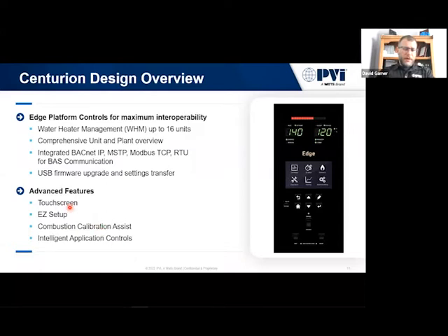The other key feature I really want to talk about is the easy setup. This is taking advantage of the O2 trim system in the unit. So let's say there's a job site, we need to do a temporary startup there. Temperature's dropping, they need hot water, something happened, and we need to turn these units on maybe a week, 2 weeks before the startup's actually scheduled. This will allow us to do a temporary startup using the O2 sensor.